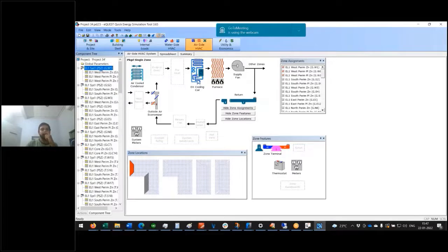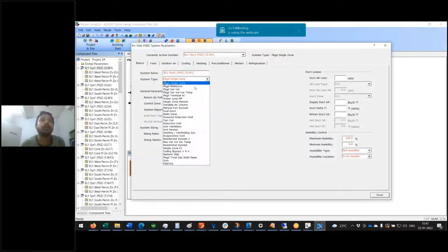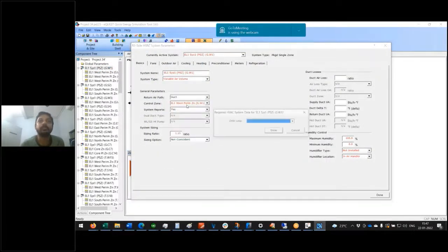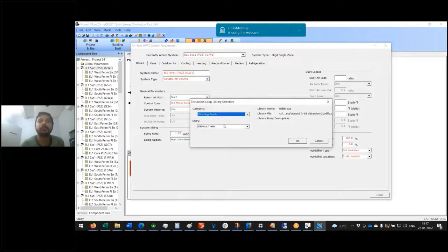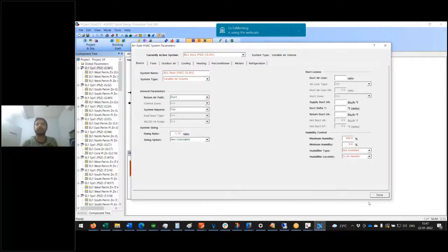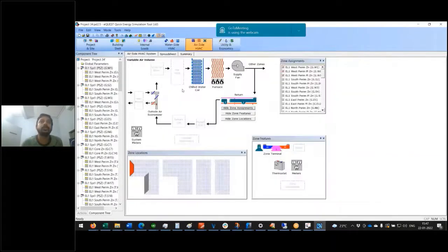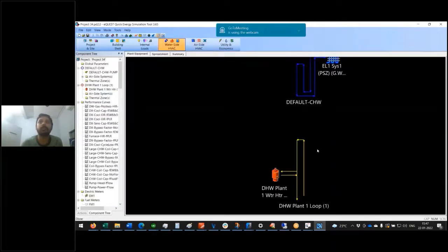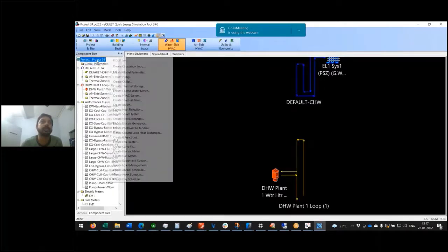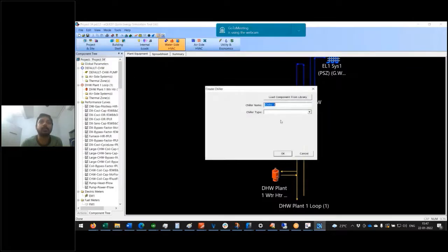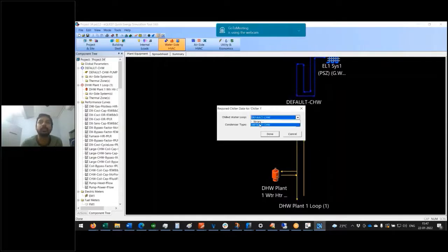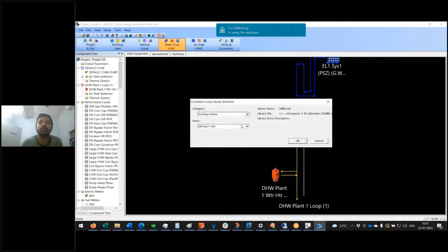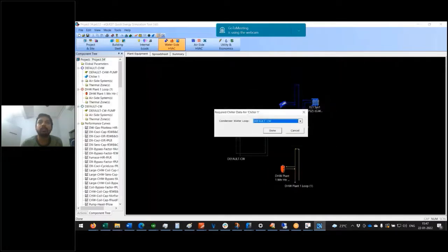Let me change this to variable air volume, library, default CHW. Okay, done. Right. So now if we make a chiller, it will automatically get attached. Chiller type, screw. Okay, chilled water loop, condenser type, water cooled, done. Default CW. Okay, done.